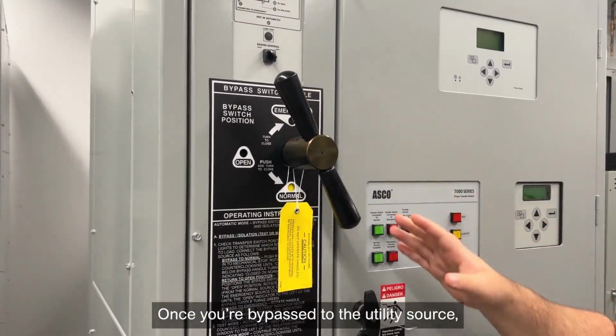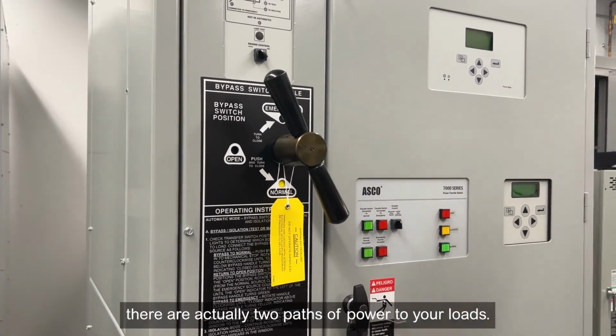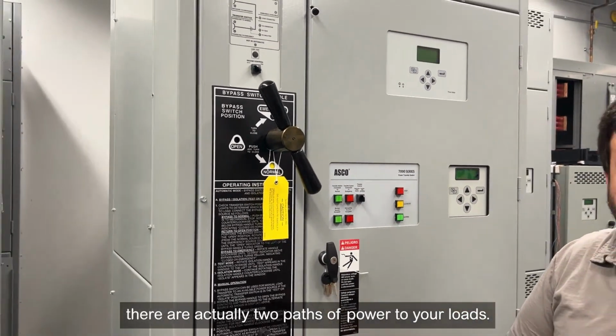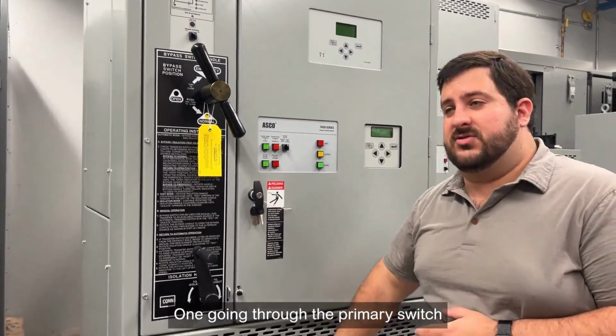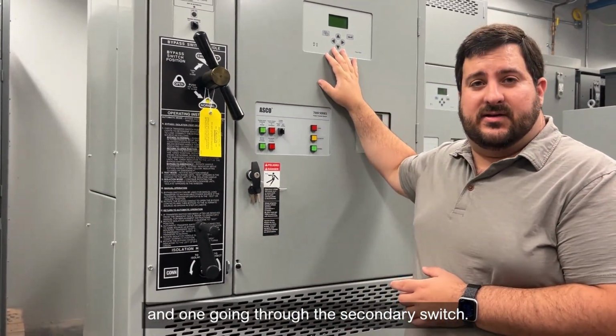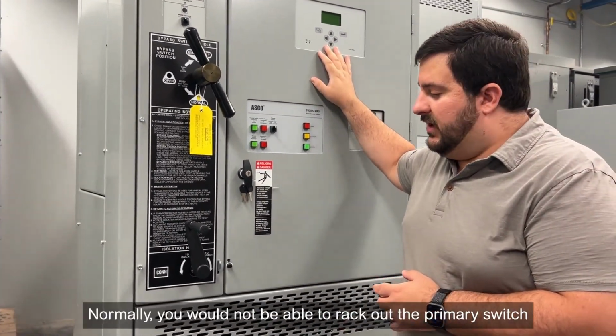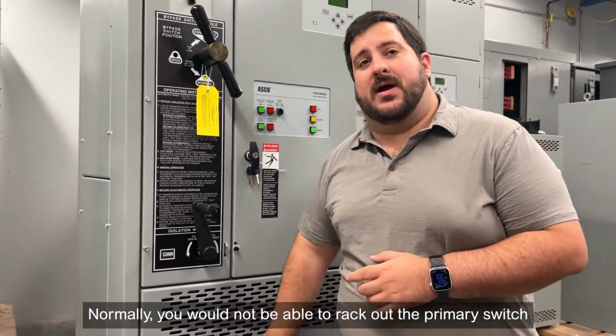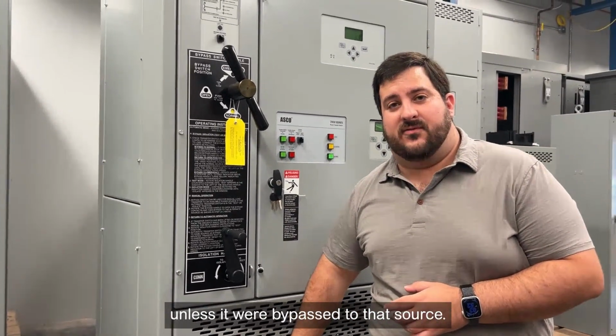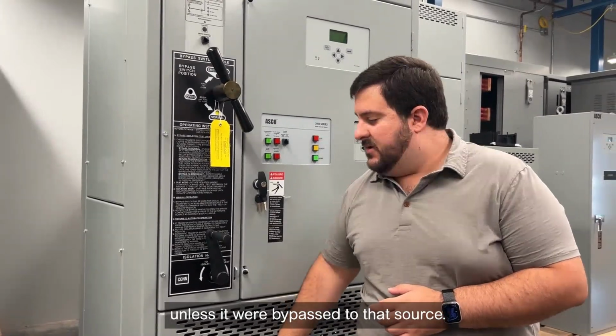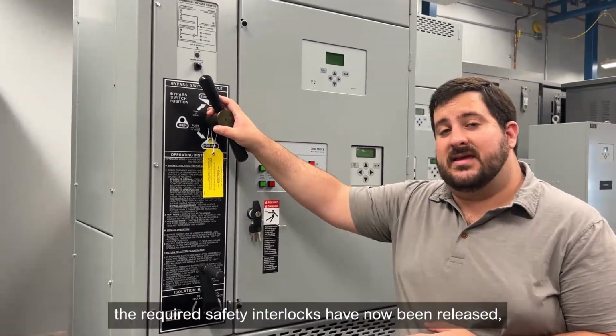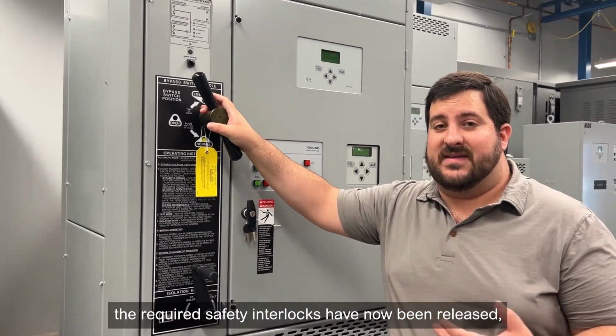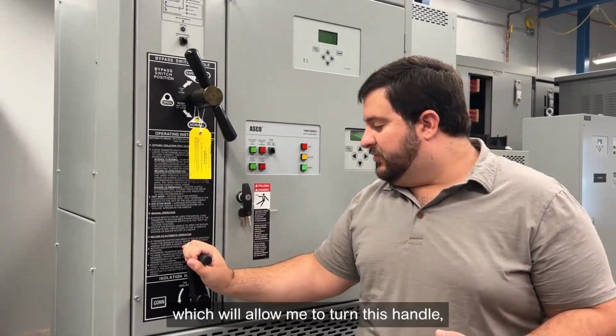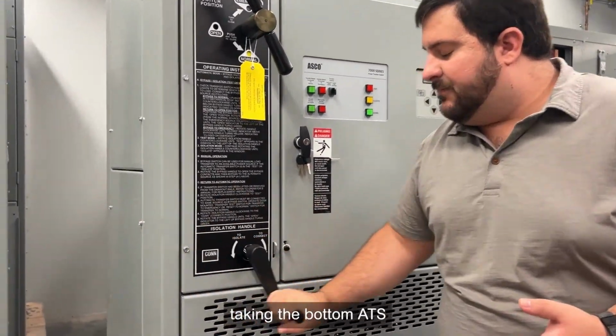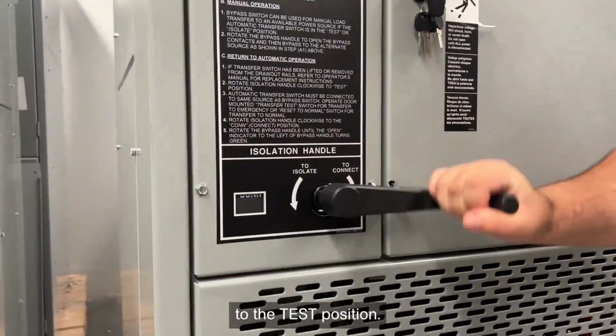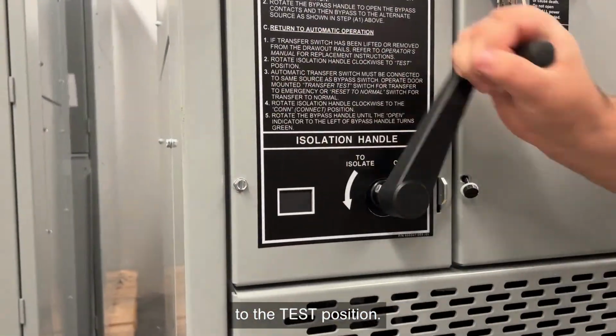Once you are bypassed to the utility source, there are actually two paths of power to your loads, one going through the primary switch and one going through the secondary switch. Normally, you would not be able to rack out the primary switch unless it were bypassed to that source. But because we are bypassed, the required safety interlocks have now been released, which will allow me to turn this handle, taking the bottom ATS to the test position.